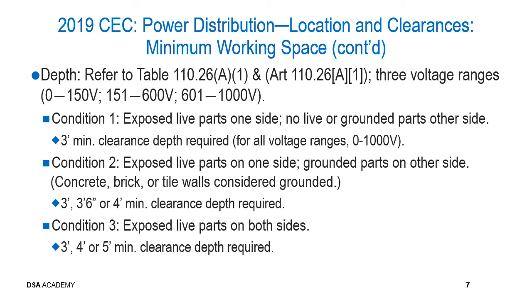Now there are basically three conditions that are identified in the California Electrical Code, which also dictate the minimum working spaces that are required in front of equipment. Condition 1 is a condition where you have exposed live parts on one side of the room and no live or grounded parts on the other side of the room. And in these conditions, condition 1, 3 feet minimum clearance depth is required. Now this applies for all voltage ranges from 0 to 1000 volts in condition number 1.